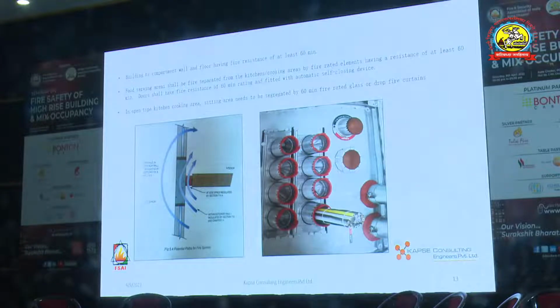Ceilings and shafts. This is the major reason for fires in these buildings. Shafts and ceilings. People are very careless about carrying out passive cables, pipes, conduit pipes, PVC pipes. I've seen rainwater pipes coming vertically down a building of about 20 floors, coming inside through the floors, and there is no sealing. And they say that around the rainwater pipe I have covered, but it doesn't help, because the PVC pipe will burn and the rainwater pipe itself will leave a hole, and that hole cannot be sealed.